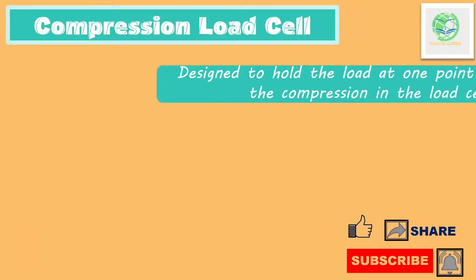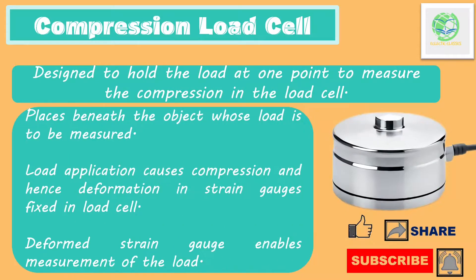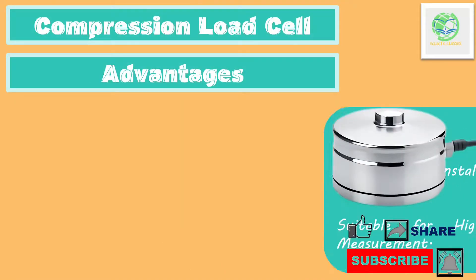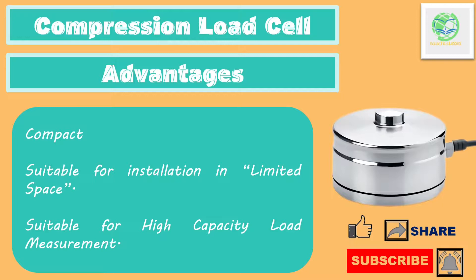Compression load cells are designed to hold a load at one point to measure the compression in it. A compression load cell is placed beneath the object whose weight needs to be measured. As it is below the object, it gets compressed due to the weight of the object. Due to this compression, the strain gauges in the load cell get deformed, resulting in an electrical signal for load measurement. Advantages of compression load cells are that they are quite compact and suitable for applications where space is limited, and they are suitable for even very high capacity loads.